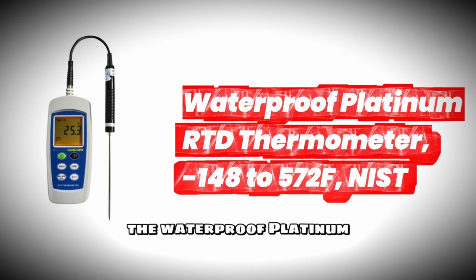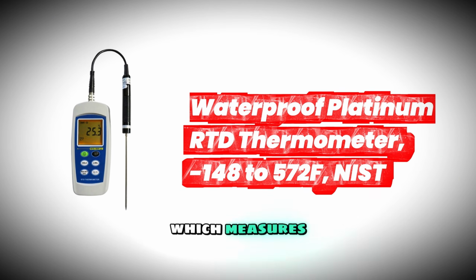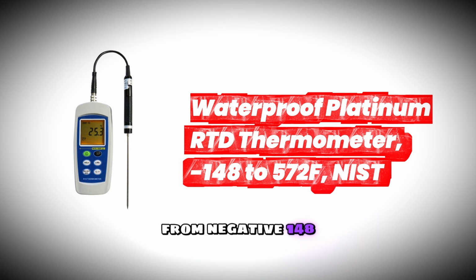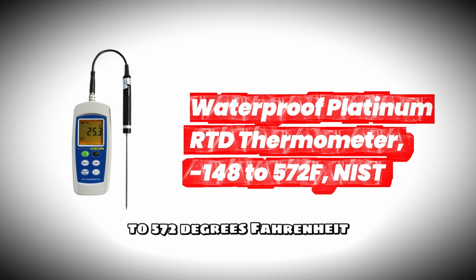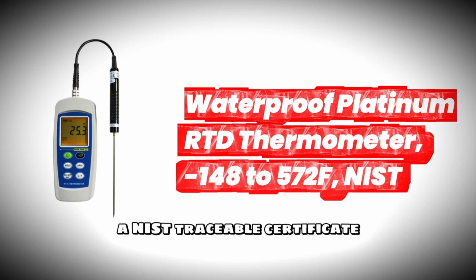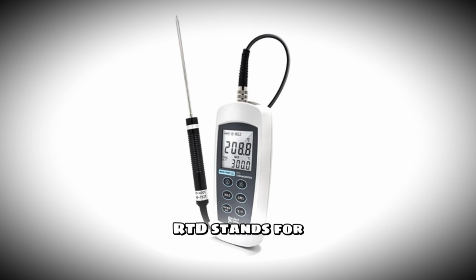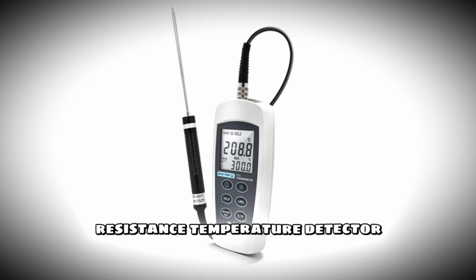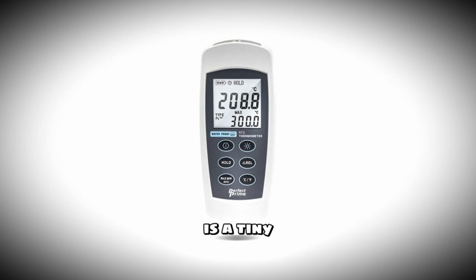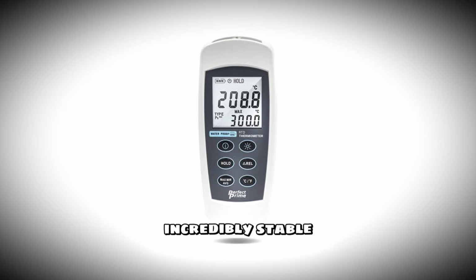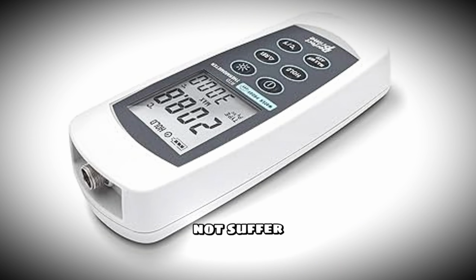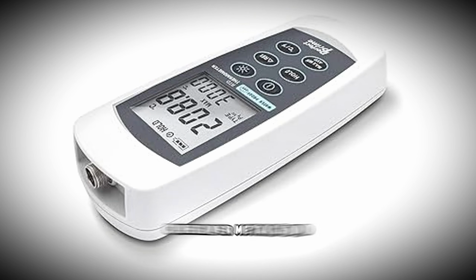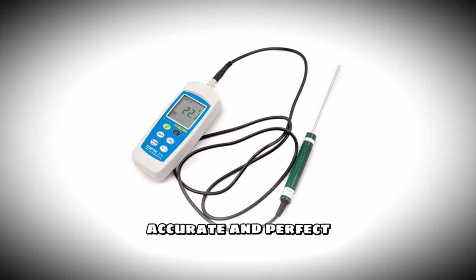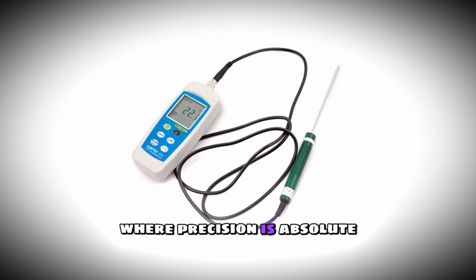First up is the waterproof Platinum RTD thermometer, which measures from -148 to 572 degrees Fahrenheit and comes with a NIST traceable certificate. RTD stands for Resistance Temperature Detector. Inside the tip of this probe is a tiny piece of pure platinum. Platinum is incredibly stable, meaning it does not suffer from the same electronic drift that cheaper metals do. It is highly accurate and perfect for laboratory use where precision is absolute.